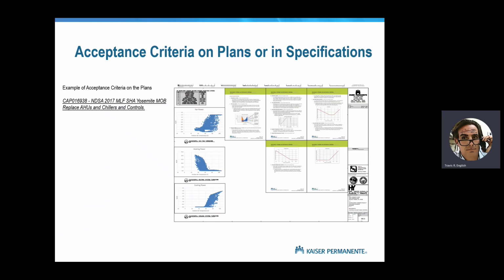But the point here is that these acceptance criteria make things objective. They make things numeric. We're not going to accept the building because the design engineer saw the fan spinning and thinks that they're working right. Or we're not going to decline the building. We're not going to hold the building up because the commissioning agent thinks that the VAV is off. We're going to accept the system when the fan power is below 0.3 watts a square foot. And we're not going to accept the building until the fan power is below 0.3 watts a square foot, right?